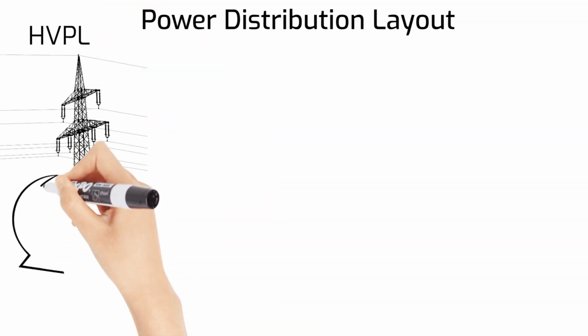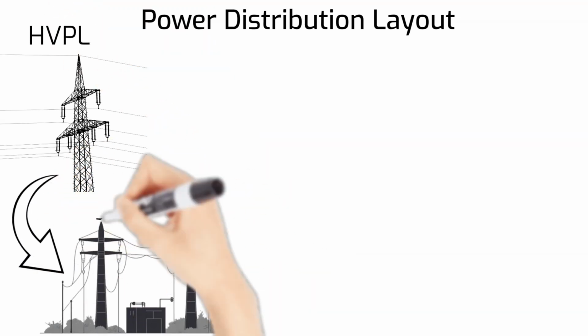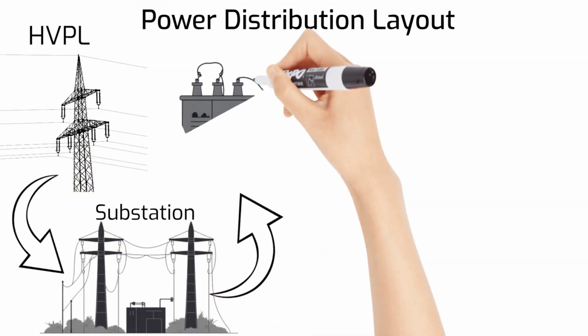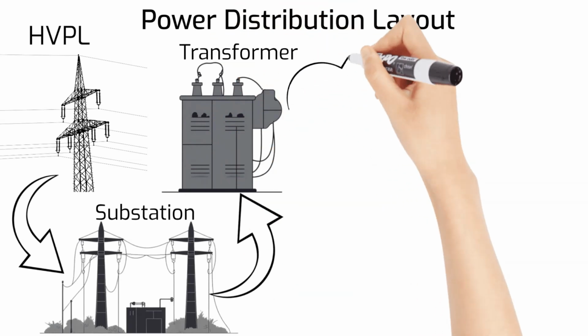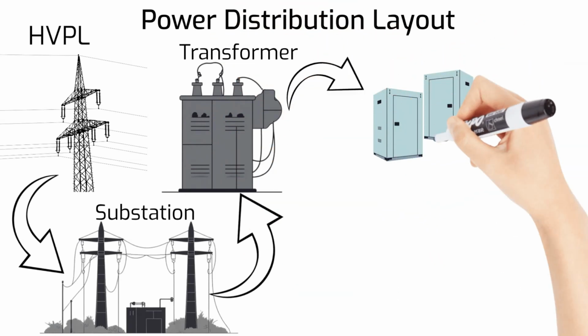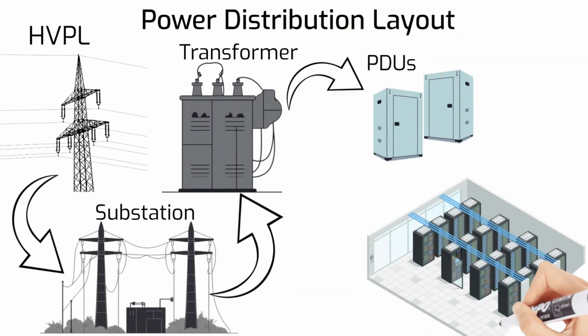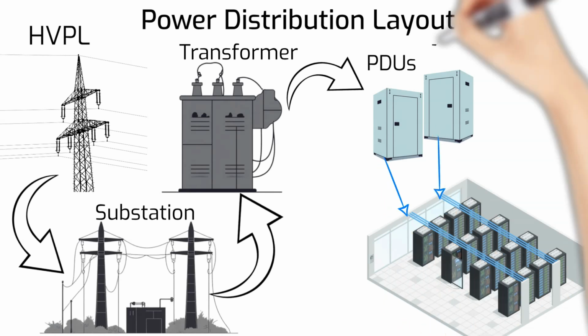Power is the lifeblood of a mining farm. High-voltage power lines supply the power to local substations. Then power is allocated to transformers which step down the voltage. Next, power distribution units feed each row of server racks in a Bitcoin mining facility. The farm connects to a high-capacity utility line, often using a dedicated transformer provided by a supplier like Raptor Power Systems to handle multi-megawatt needs.